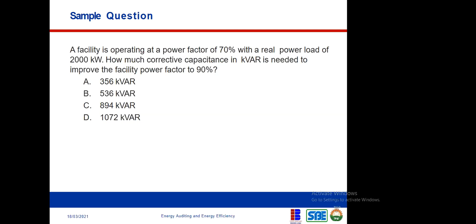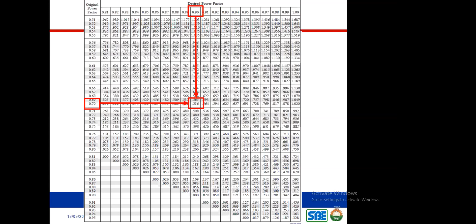So we'll solve this together. If you remember, we have a power factor of 0.7, and we desire it to be 0.9. If you look at the coincidence where 0.7 meets 0.9, you finally have 0.536. So that becomes your table factor. All you need to do is to take this table factor and multiply it with your true power, which was given as 2000 kilowatts.